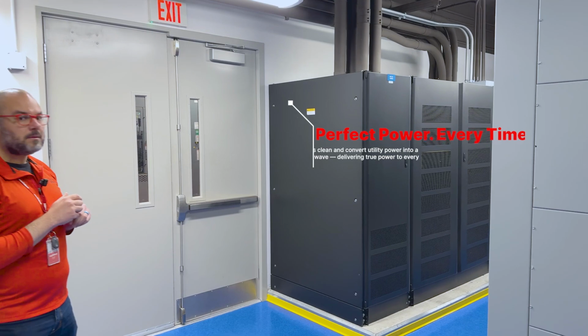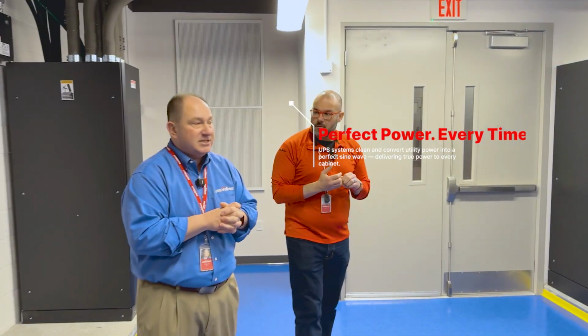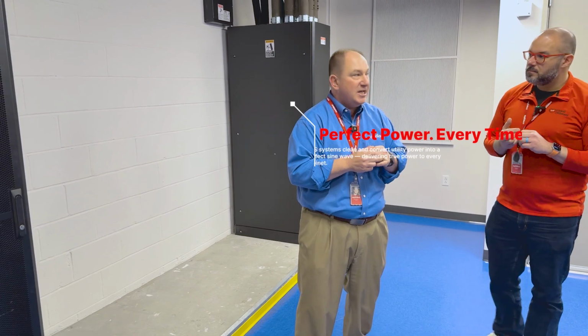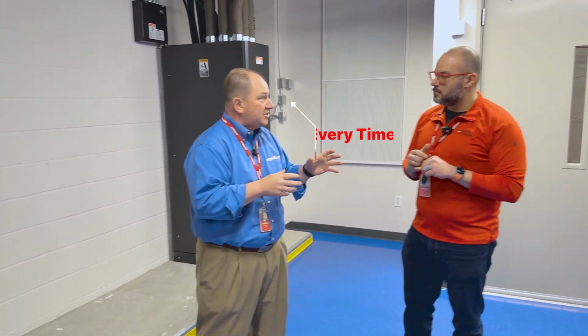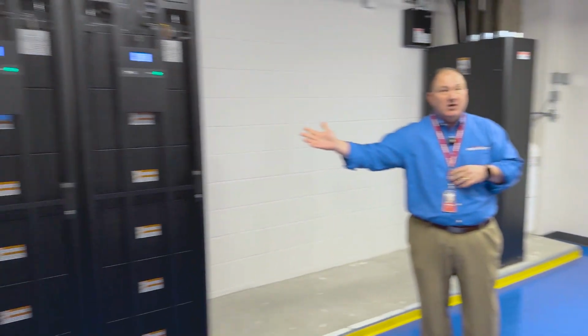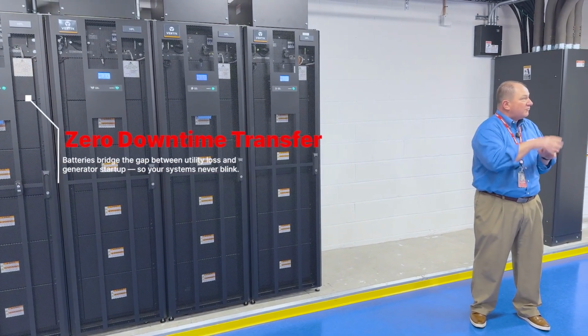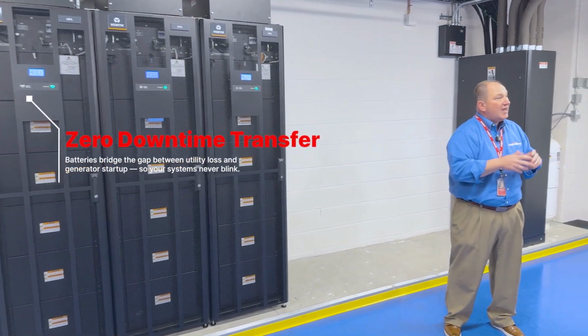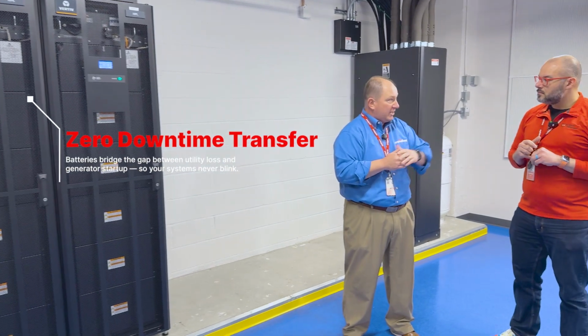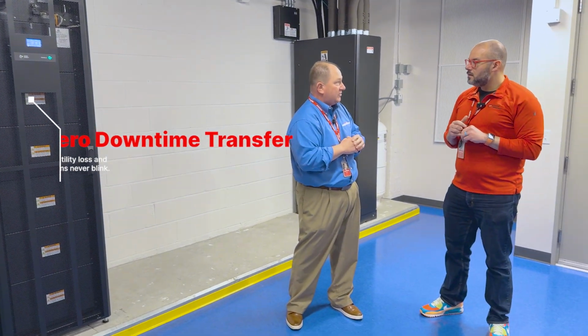Over here you'll see our UPS system, an uninterruptible power supply. Basically what this does is take the current waveform in from the utility company, which is AC. It cleans that up, we change it to DC and charge our batteries, then change it back to AC and feed it out to the raised floor, to the PDUs and to the customers. That allows the waveform to be perfect when it goes out to the raised floor and out to the cabinets.